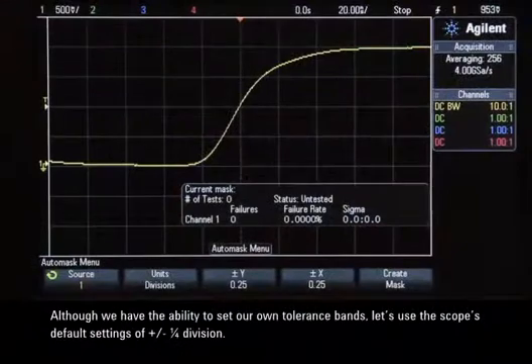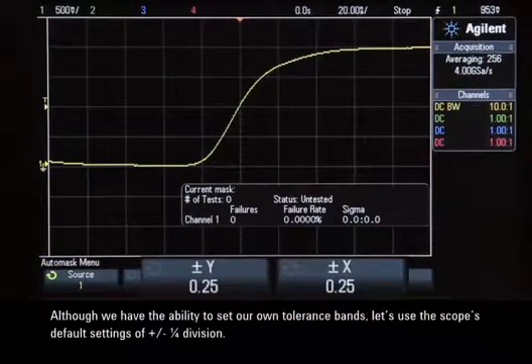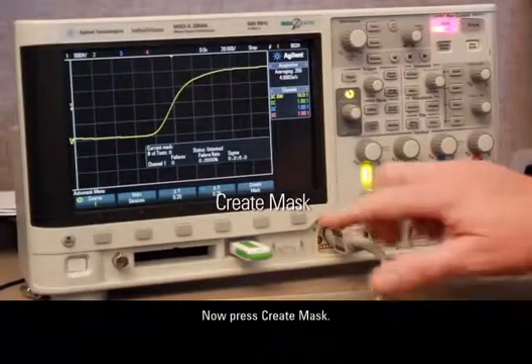Although we have the ability to set our own tolerance bands, let's use the scope's default settings of plus and minus a quarter division. Now press Create Mask.